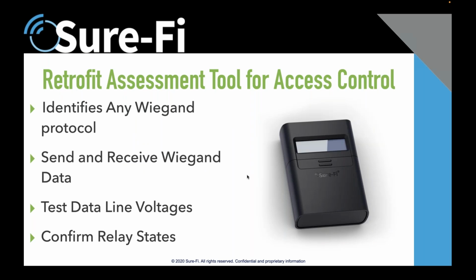This is really nice to do some troubleshooting on existing access control systems. There's times you go out on a service call, or take over access control on a business or a place where you don't know what the wiring's like, or a lot of other things. If something isn't working, this can help you identify where the problem is. Is it a bad reader? Is it bad wire in the ground? Is it a bad input or output on the access control panel?